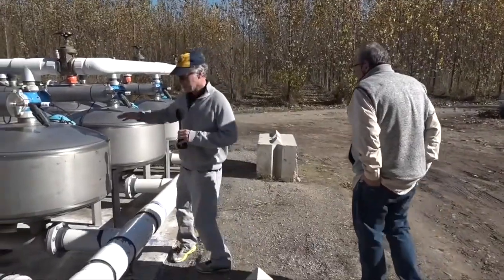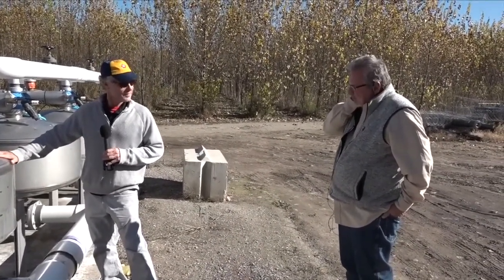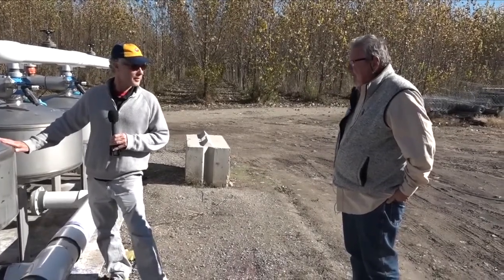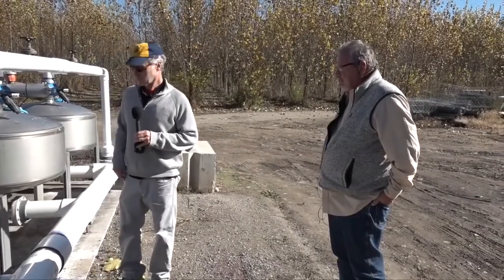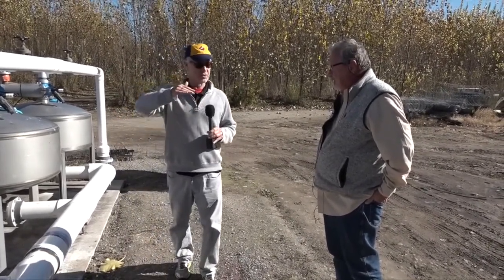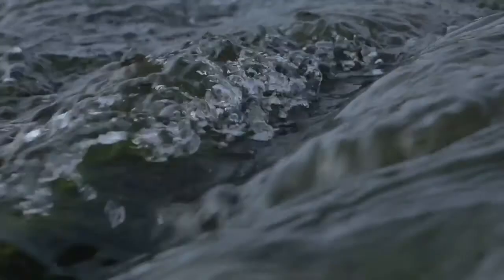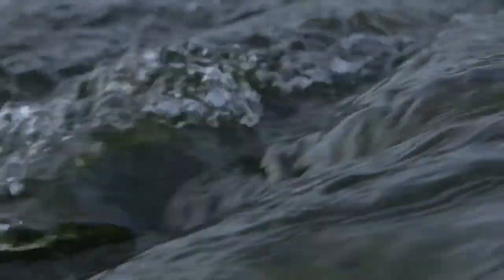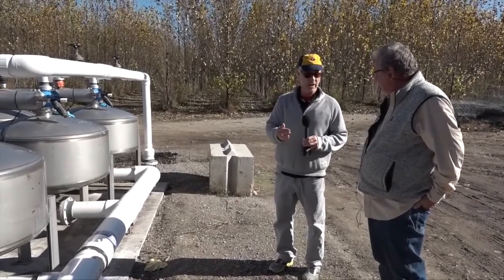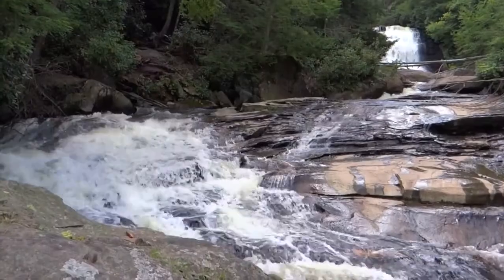What we're looking at here are massive filters — sand filters, but they actually don't use sand. They use ground garnet sand, which is heavier than sand so it doesn't bleed out when you back flush these. Our effluent quality is really high — we clean the water up to really high levels. By industry standards, this water is cleaner than gray water. This is filtering over a million gallons of water a day, reducing the amount of phosphorus and nitrogen that create algae and harm the fish and the whole ecosystem of the river — removing 20 to 30 percent of those unwanted water nutrients.